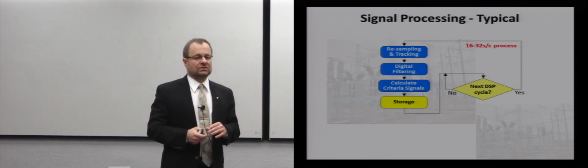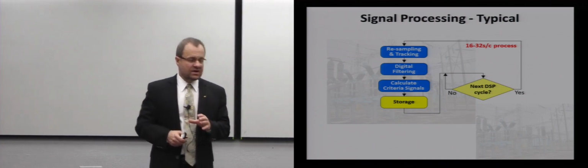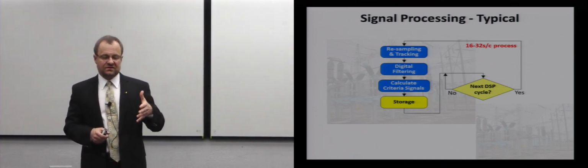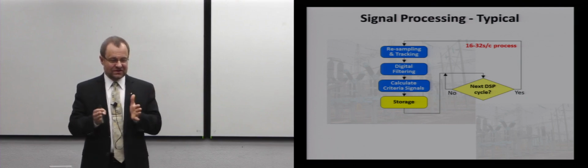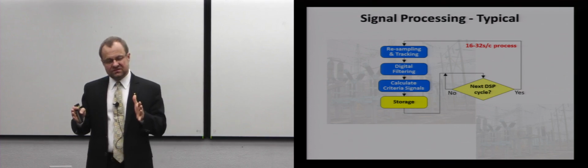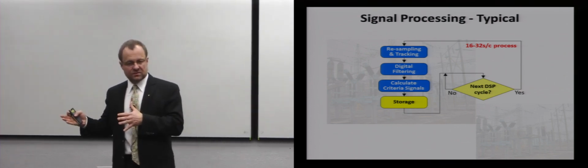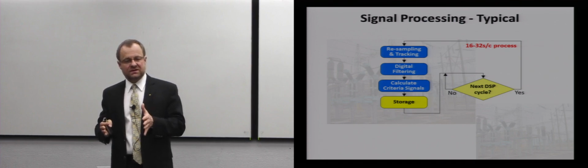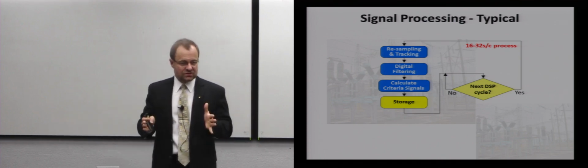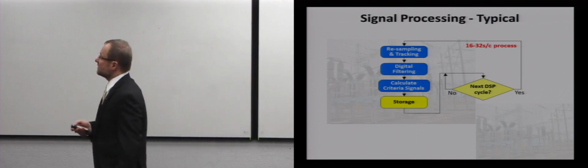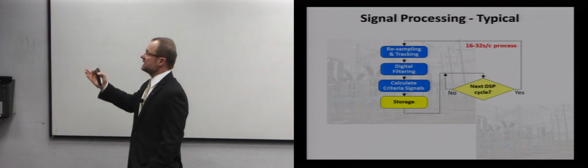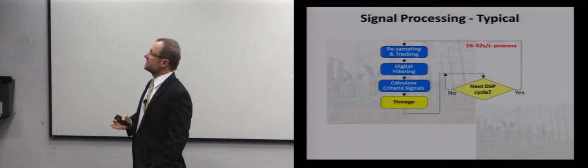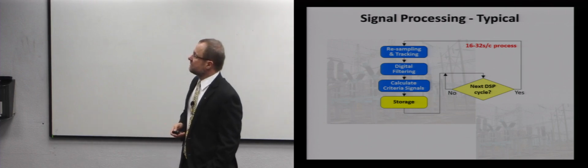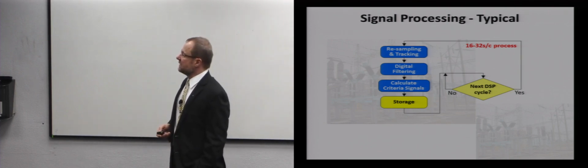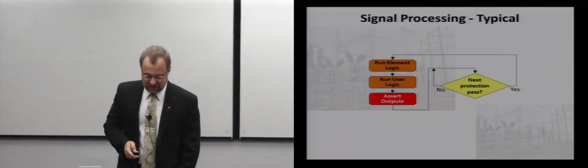That's not the ideal solution, because if you ever program a microprocessor, you don't want it to be at the mercy of some other process and start changing your execution rate, right? But because the changes in frequency are so small, historically this is what we did. We allow the system frequency, as we measure it, to adjust our execution rate. And running it not at 8 kilohertz, but only at, say, 16 times a cycle, at 1 kilohertz effectively, or 2 kilohertz around, allows us to calculate more stuff. So this is typically done in DSP-like silicon.